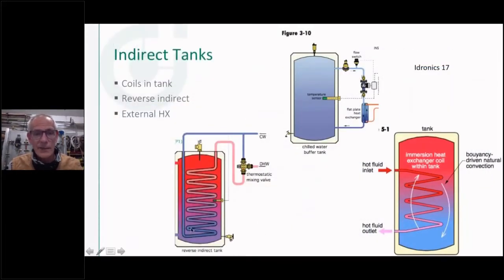So yeah, you can do a lot of things with those. And here's indirect tanks, just a heat exchanger if you think about it. So this is what's called a reverse indirect, where the boiler water would be in the tank, and then the coils, the copper coils, or sometimes stainless, is where the domestic water goes. So it's almost like an instantaneous tankless heater, in that the water gets heated as it goes through these loops inside there, and it comes out at the temperature. And those can be nice buffer tanks also.